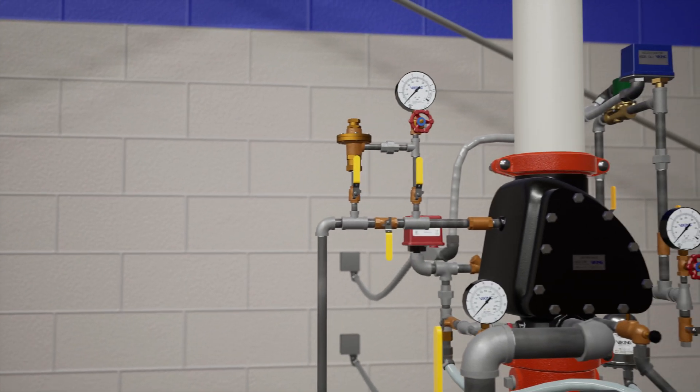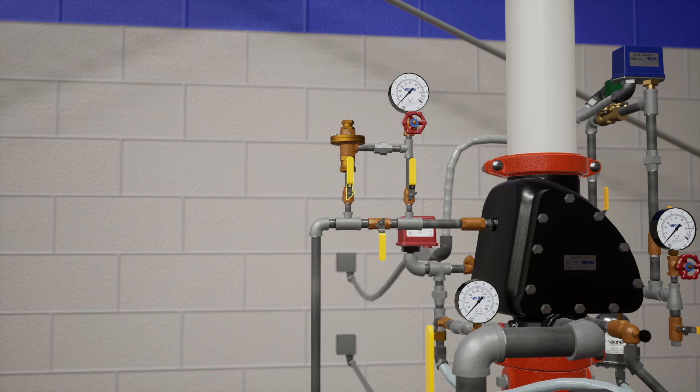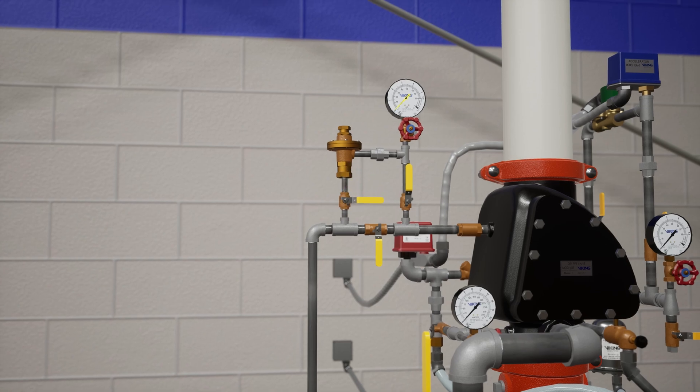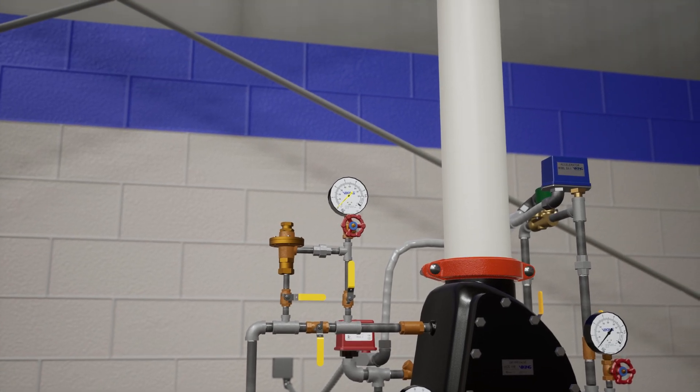Next, shut off the air supply to the system by closing the quarter-inch isolation valve before the air pressure maintenance device and verify there is no pressure showing on the air supply pressure gauge.